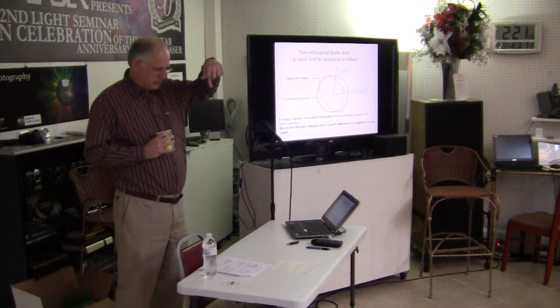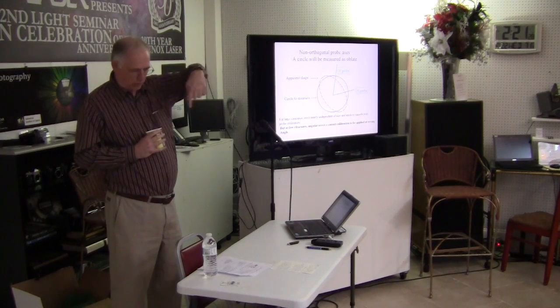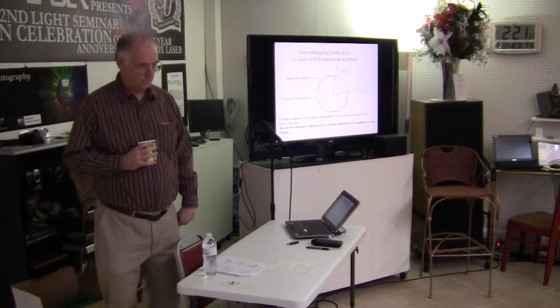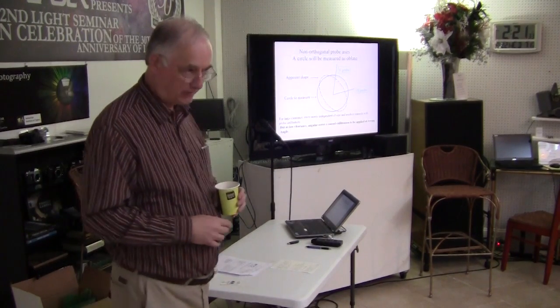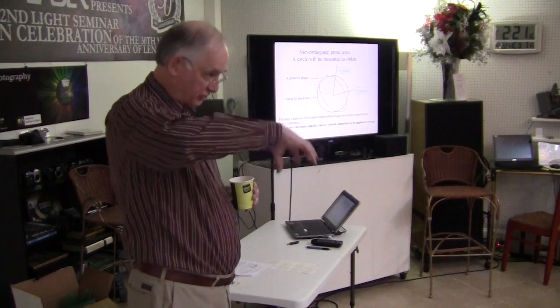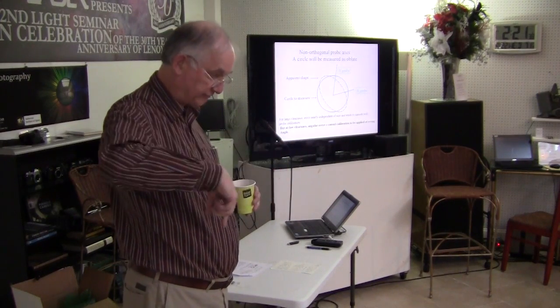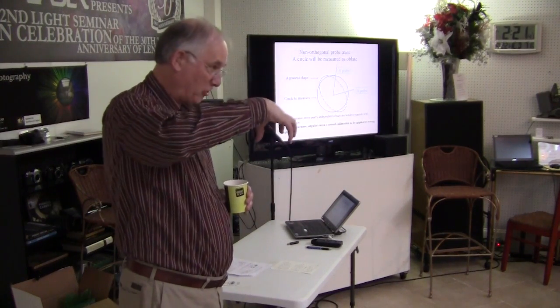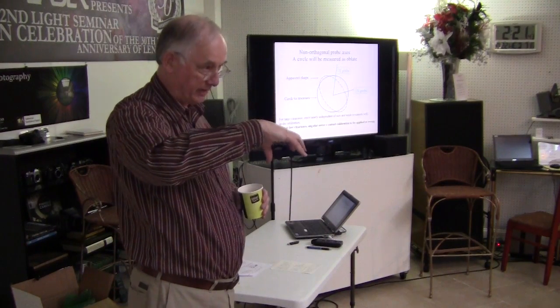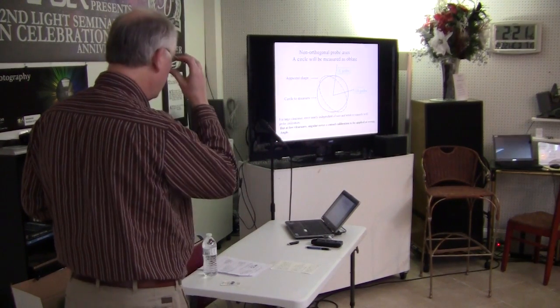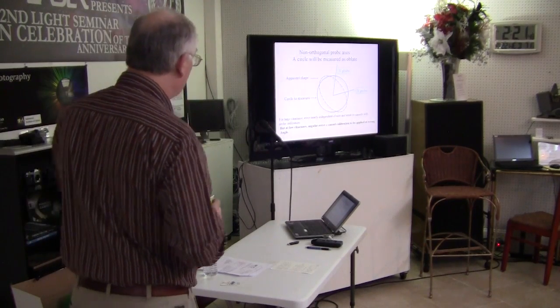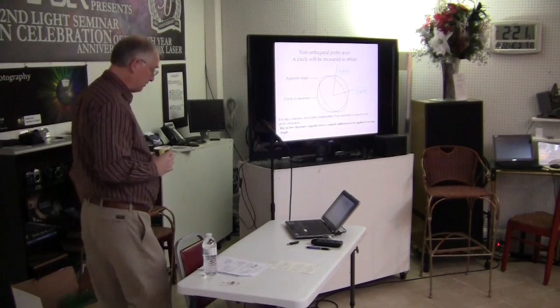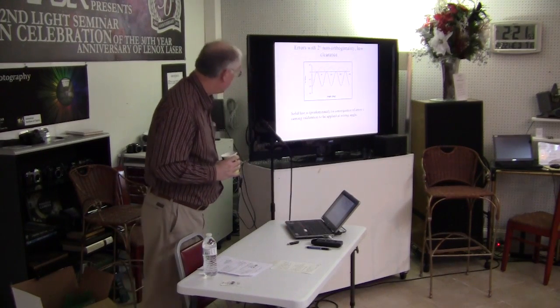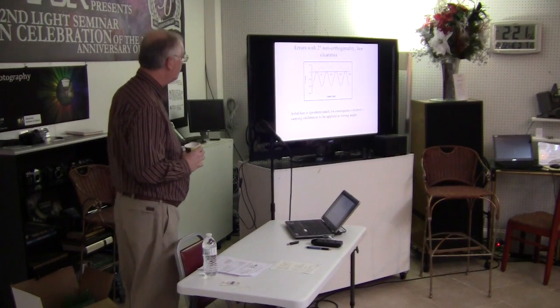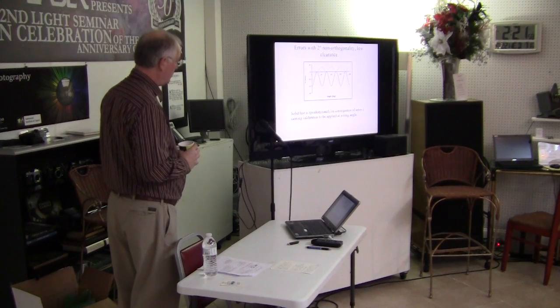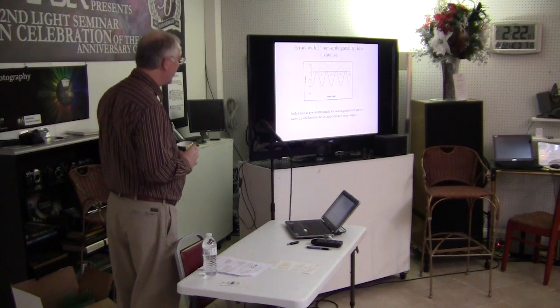The next thing is, the probes themselves aren't always circular. The old CMM probes on touch-trigger classically had a 3-lobed error. They measured something really, really round, and it would measure it as having 3 lobes, because internal to the probe the mechanisms weren't squared up and they did funny things. These were all studied and modeled and all that good NIST stuff, and you can see the sort of errors you get. Again, 20 nanometer type stuff.